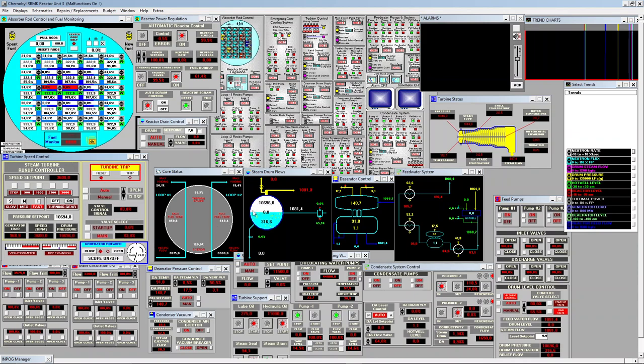Let's check drum pressure. It's 10,000 kilopascal, 10 megapascal. It's a bit high, so it means we could open a bit more the valve control signal of the turbine to try to generate a bit more power. Now we're generating 969 megawatt.